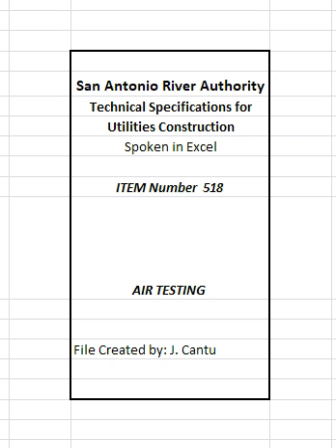518.3. Test procedures. The procedures for the low-pressure air test shall conform to the procedures described in ASTM C828, ASTM C924, ASTM F1417, or other appropriate procedures, except for testing times. The test time shall be as outlined in this section. Clean the sewer to be tested and remove all debris where indicated. Wet the sewer prior to testing.